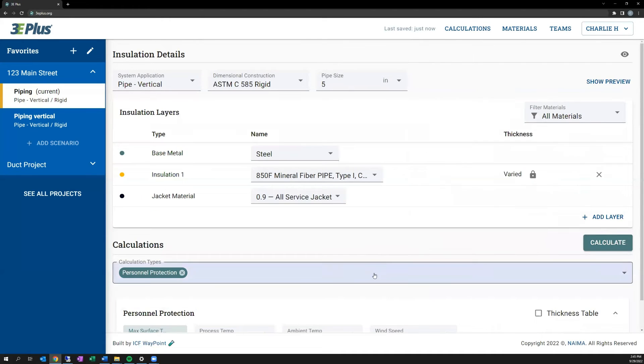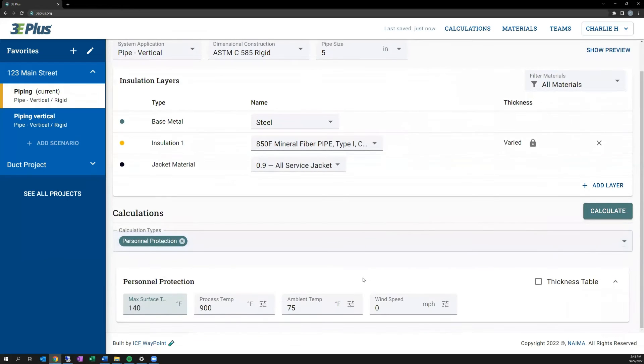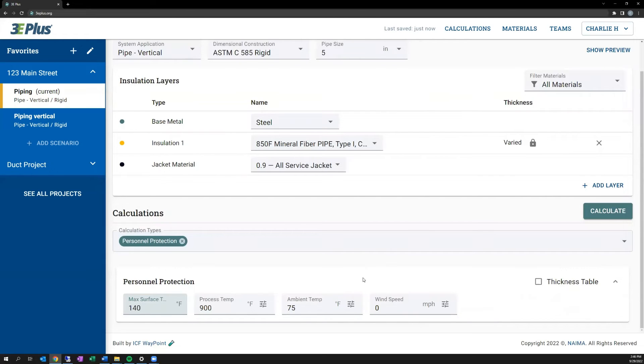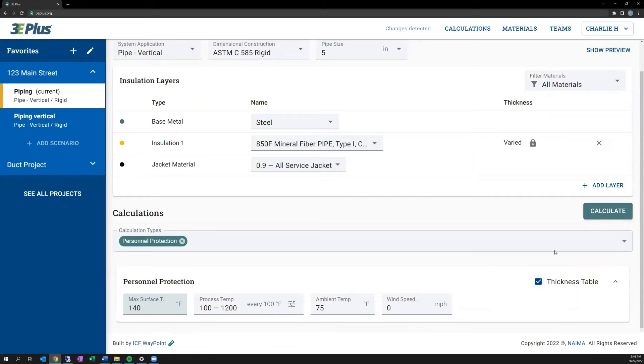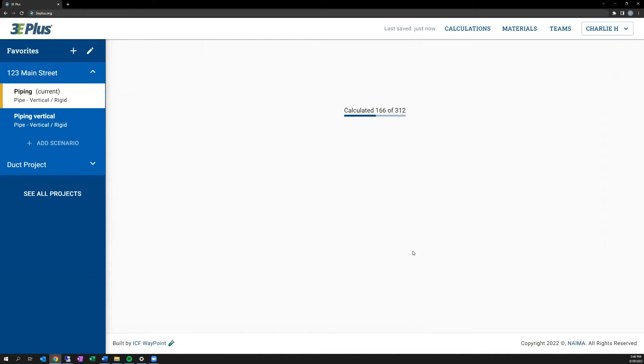Additionally, a new feature that was in the original 3E Plus in a more limited form is that you can now create a thickness table to use in specifications based on these target calculations. So for personnel protection, it would create a table over a range of pipe sizes and process temperatures. We can say that when using this amount of insulation, you'll meet the goal of being less than 140 degrees. So it does all that hard work for you, iterative work of changing pipe sizes, changing process temperature, and does it automatically over a range.